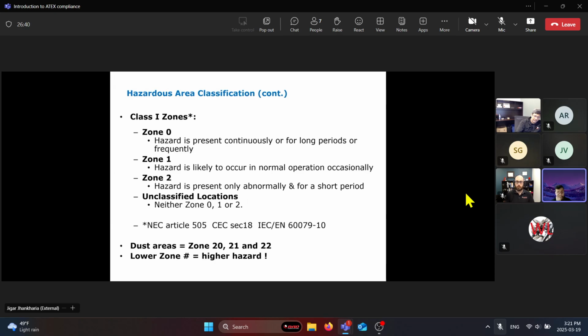So for Zone 0, there's only, I believe, 3 methods of protection that you can achieve to get Zone 0 certification. One is through intrinsic safety. The other is through encapsulation. And the third one is only applicable for catalytic sensors through the flameproof method of protection. And I think there is the option of optical radiation, but again, doesn't apply to your product. And I'll show you the list of standards after this.